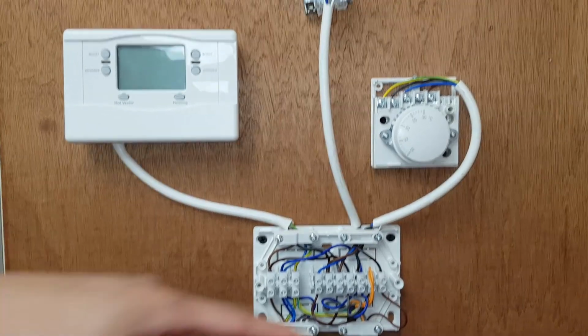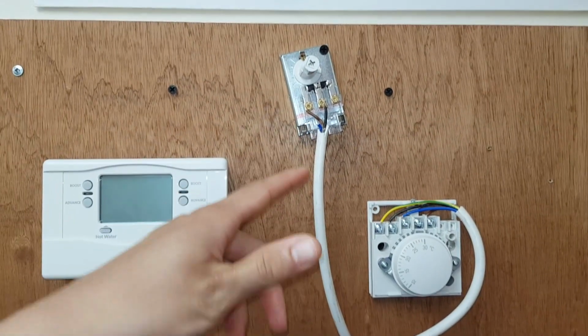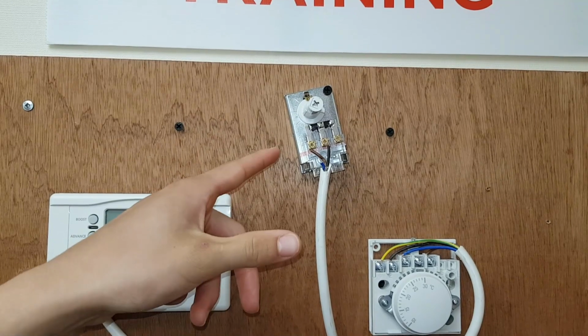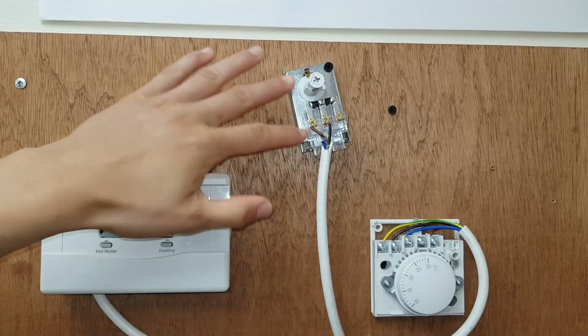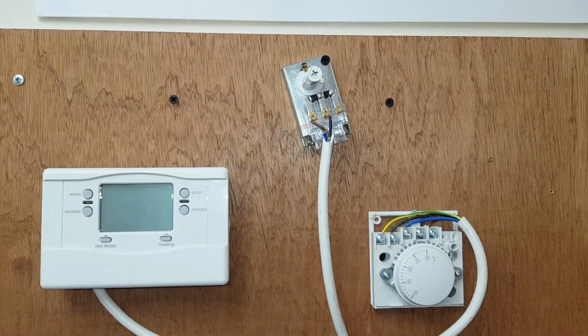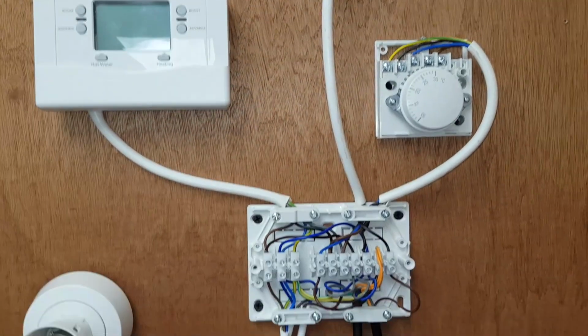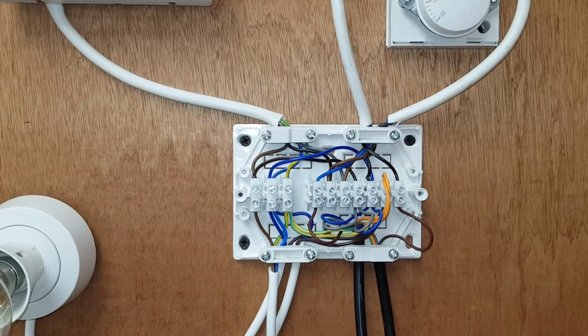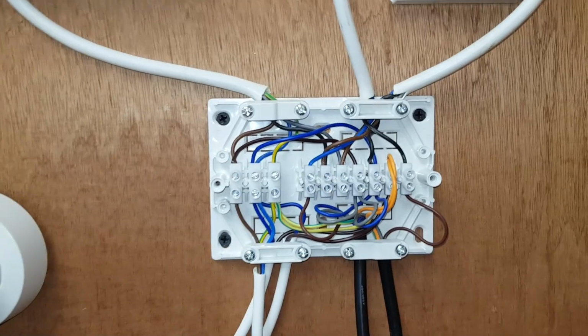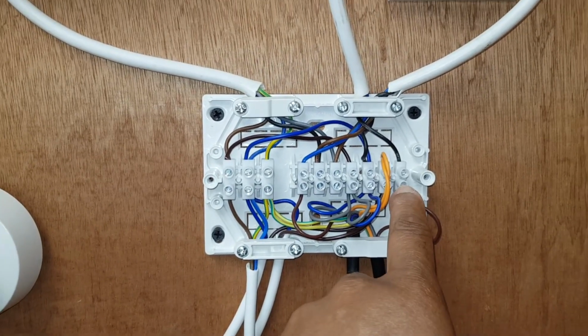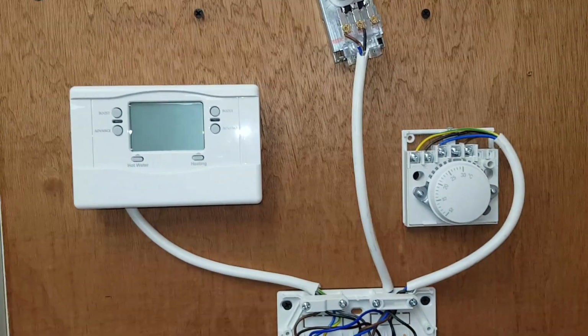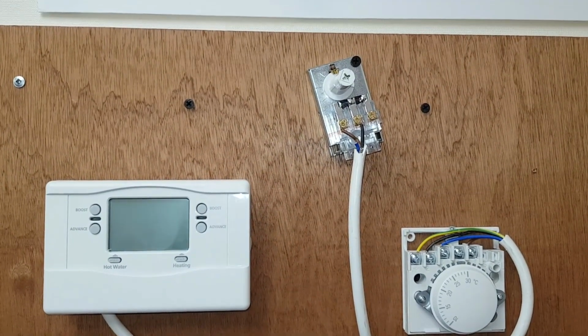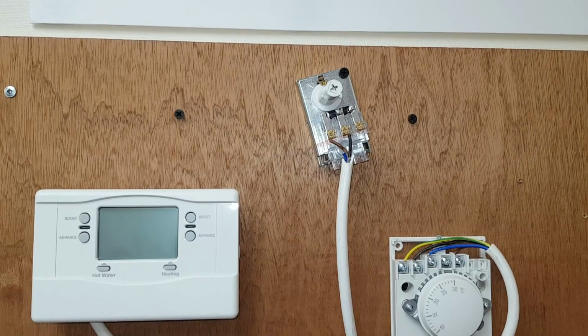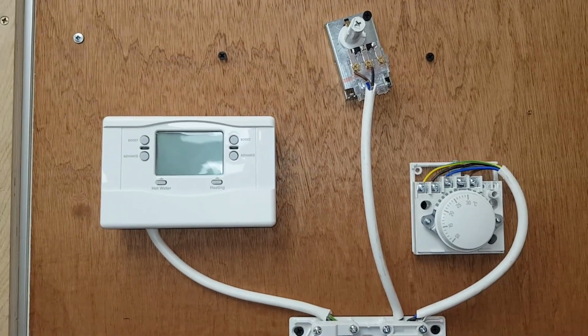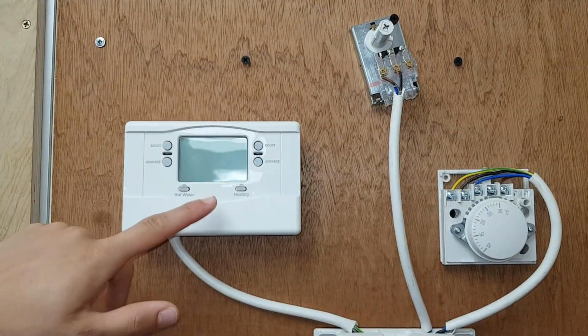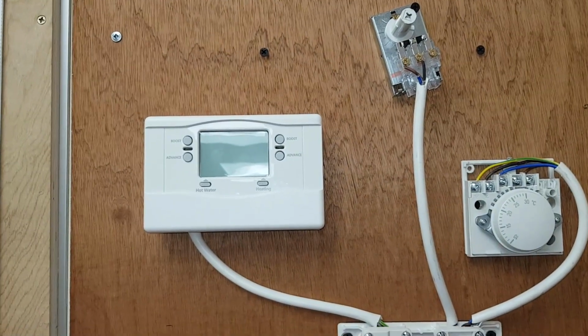Okay, so we go back up to our cylinder stat and we'd link out again. And if we did get power, it would mean that this is gone. Okay, good. Now, another one. So again, we've got no power here. Now you link this out, so that didn't work. So what would you be looking at next? Well, you go to where this came from, which is the programmer. And it would mean that the programmer's gone.